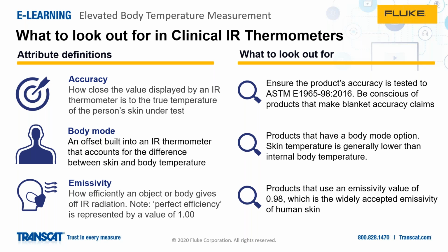So on the accuracy side, you want to ensure that the product's accuracy is being tested to the ASTM E1965-98 standard. This is the standard that's called out in the FDA's enforcement policy and calls out what the product accuracies should be. And you just want to be conscious of products that are making blanket accuracy claims but are not referencing any of the standards that that accuracy might be tested to. When you're looking out for products, you might also look out for the ones that have a body mode option. Since your skin temperature, as we've discussed, is generally lower than your internal body temperature, you're going to want to make sure that whichever product you're using has some sort of offset to account for that.